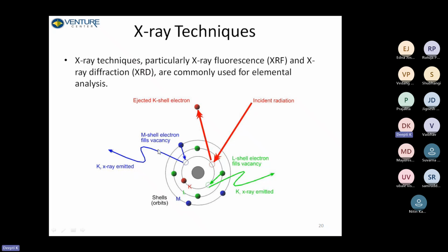Right. So the prepared sample. The advantage of an X-ray technique is that solid samples can be directly introduced. It is not necessary that the samples need to be converted into a solution form. The sample is placed in an XRF analyzer, which emits very high energy X-rays towards the sample. These high energy X-rays strike atoms in the sample and cause the inner electrons to be ejected.